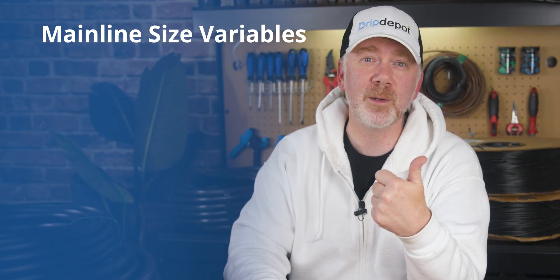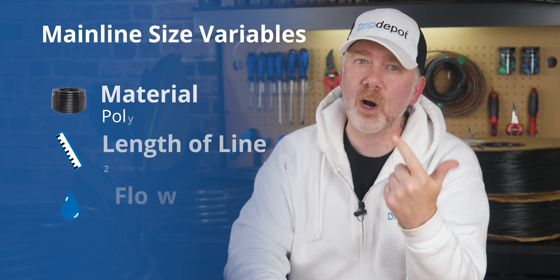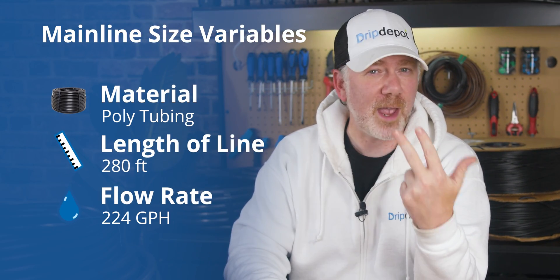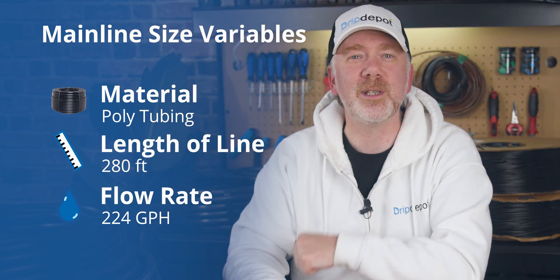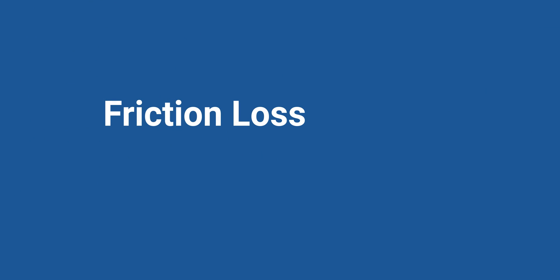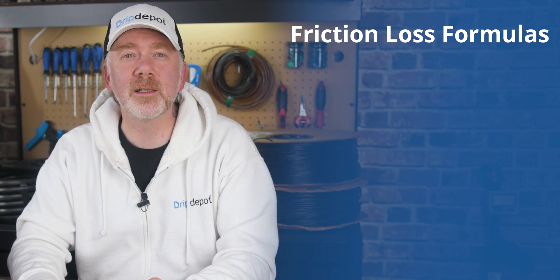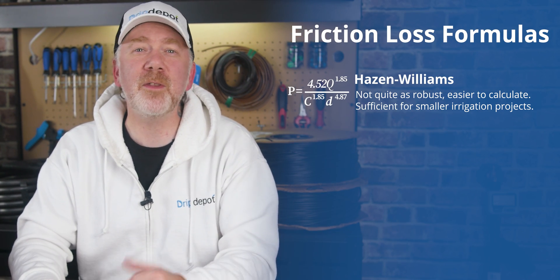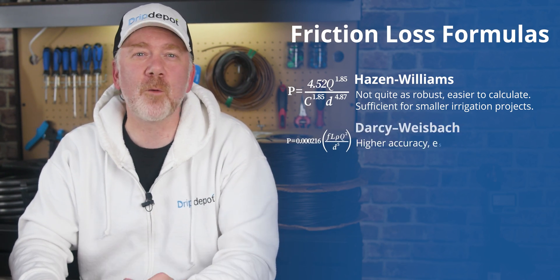We now have our three variables: system flow rate, line length, and the material we're using. Let's start using these three variables to first determine our system's friction loss. There are two formulas commonly used to determine friction loss: the Hazen-Williams formula and the Darcy-Weisbach formula. Our online calculator uses the Hazen-Williams formula.